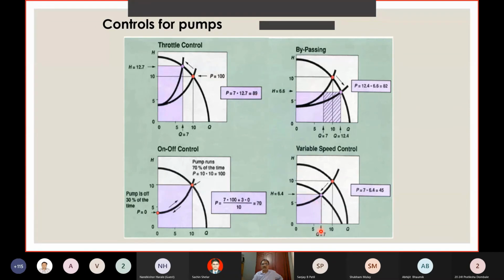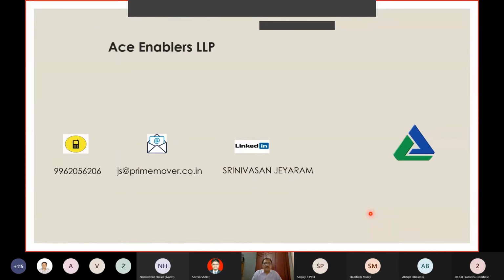But if you use a VFD and reduce the flow to 7, the pressure will not increase, it will reduce to 6.4, such that you will have as much as 55% energy saving. So I want to emphasize that in pump and fan applications where a throttle or damper is used, if you change over to a VFD and remove the throttle, valve or damper, you will find that the energy saving is substantial. It must have been the experience of some of the industry people already. The theory behind this is this. I wanted to explain this as an opportunity available. That was my last slide.